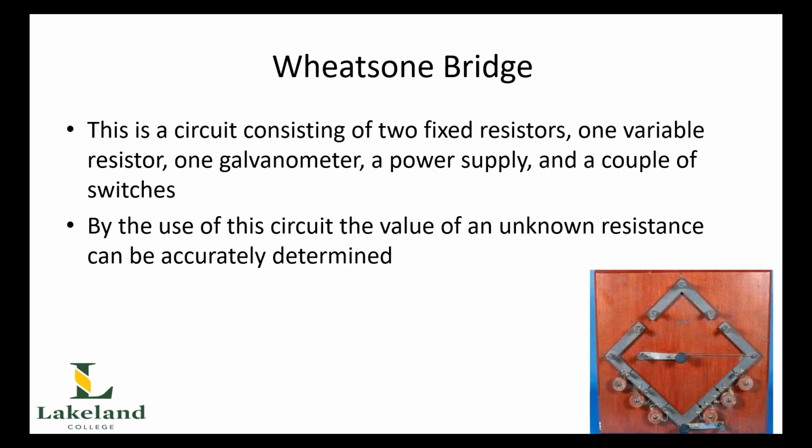Where we see these in power engineering is in the field of instrumentation, in areas like RTDs, or resistance temperature devices, or even measuring temperature, for example, as resistance and temperature are linked. That is, typically for most materials, when temperature goes up, resistance goes up. So we could determine what the increase would be by determining that increase in resistance on a bridge circuit. For further discussion of the uses of Wheatstone bridge circuits, check out Unit 9 on the 4A from 4th class, and also check out the instrumentation chapters in 3A2, as they go into the use of these types of things.